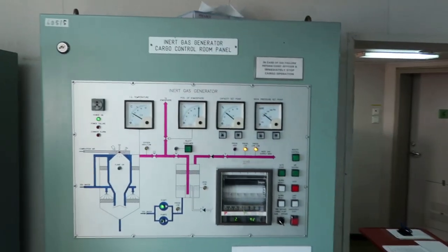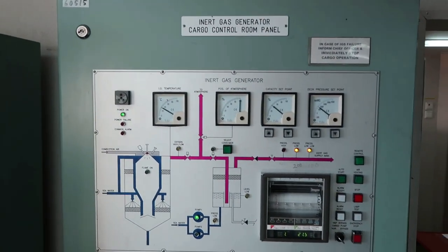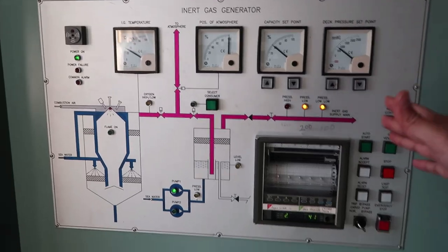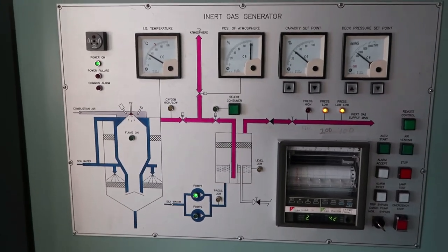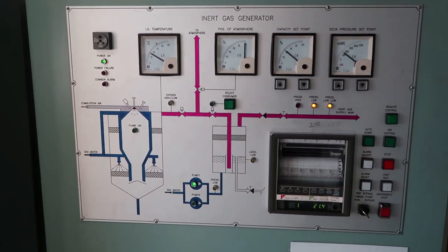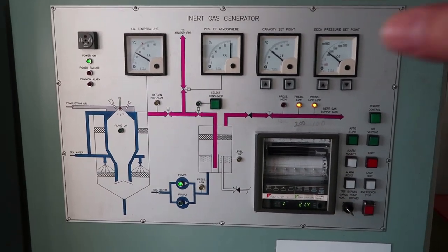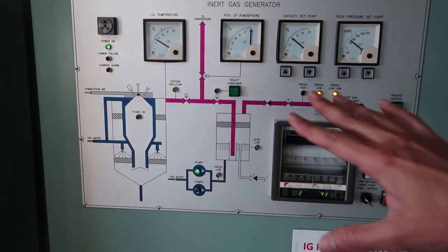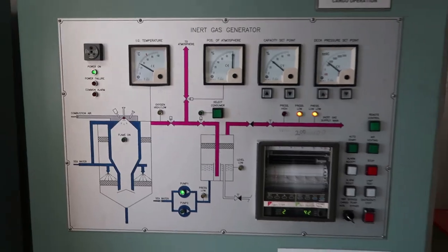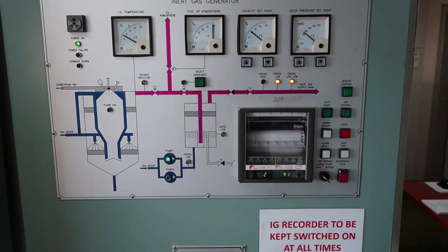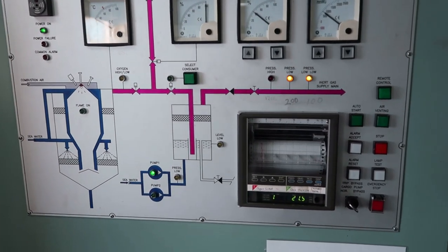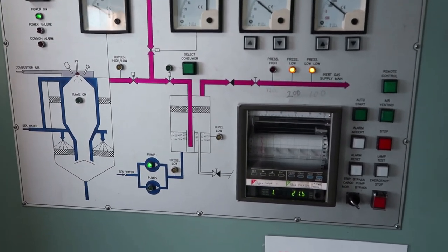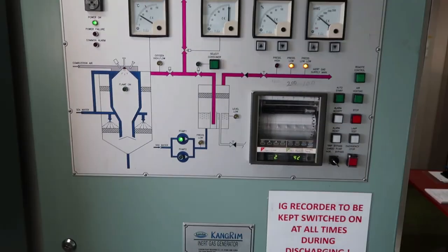This here is a separate air conditioning system given for CCR. Next to that is inert gas system. When we carry gasoline, diesel, oil etc., we are supposed to have a safe atmosphere above the cargo tank. That is achieved by inert gas. Inert gas generators supply you a gas which has about 5% oxygen. By the time it goes inside the tank, we are always supposed to keep at least less than 8%.